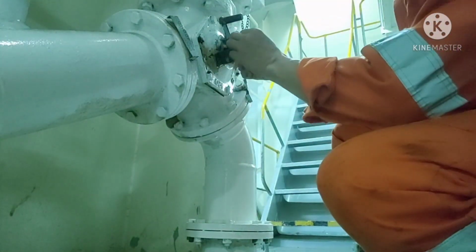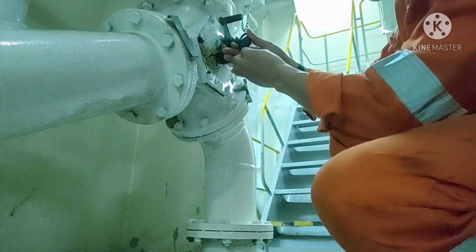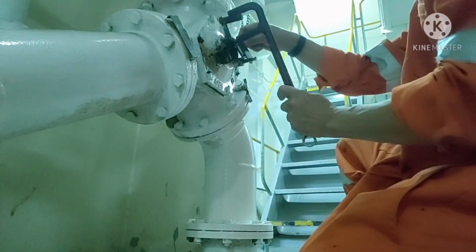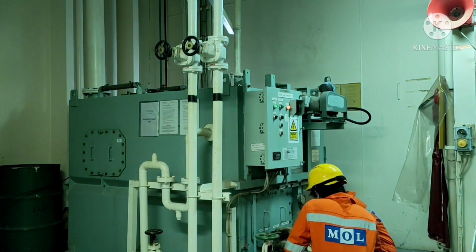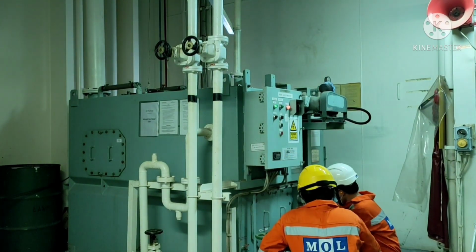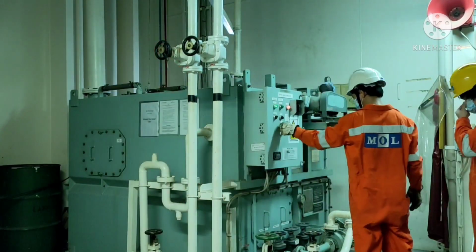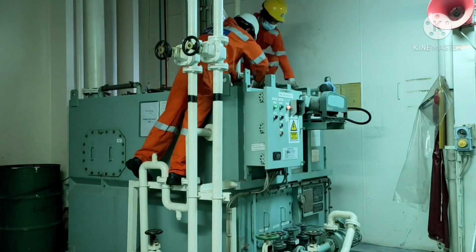So, to start with, first we have to bypass the plant. Take out the padlock, break the seal, and change over the valve. Now, the sewage treatment plant is not in service. Then proceed to the plant and pump out the three tanks: the aeration chamber, the clarifier or settling tank, and the chlorination tank. When those three chambers are emptied, stop the air blower and open each manhole.